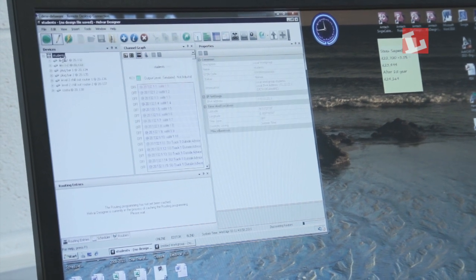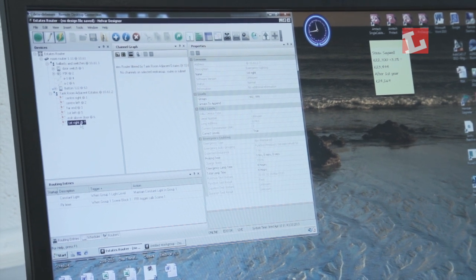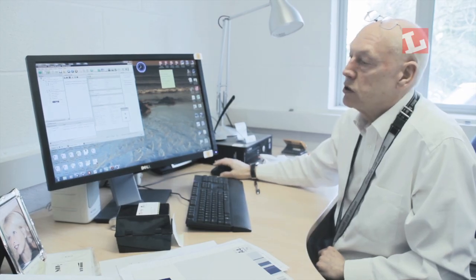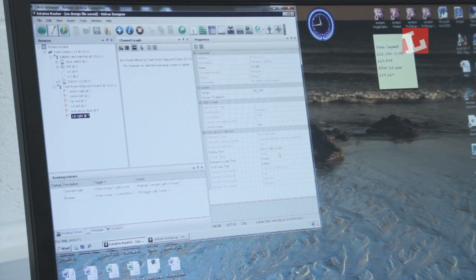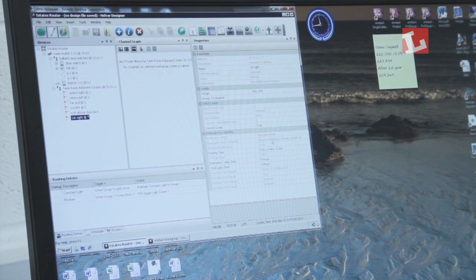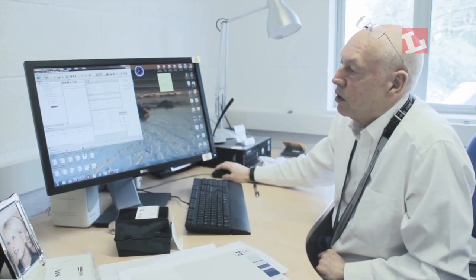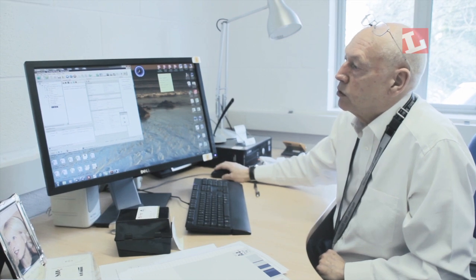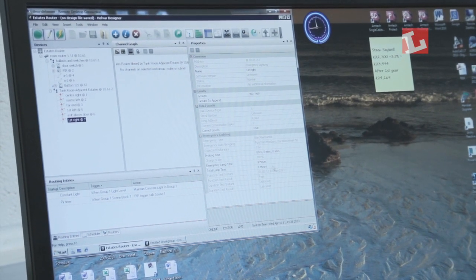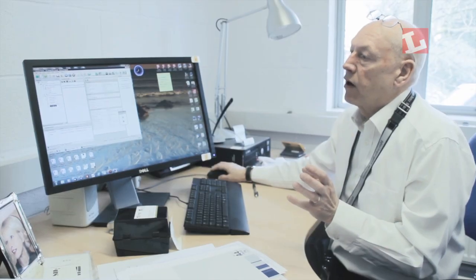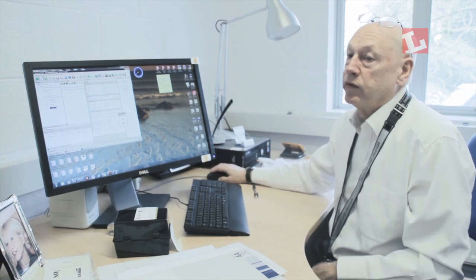The system also does emergency lighting self-test. If I click on one of them, it gives me all the information about that emergency light — it tells me it passed its function test on the 10th of March 2013, the charge state is 100%, and the total lamp light is four hours. It also gives me all the DALI information and a location. Once that test is carried out, it puts it back into a database so you can recall it for future use.